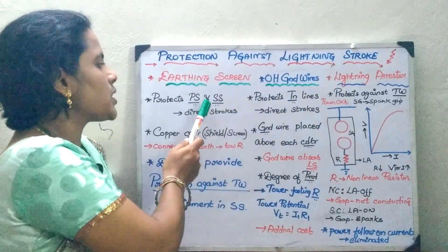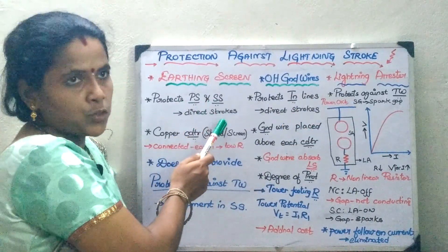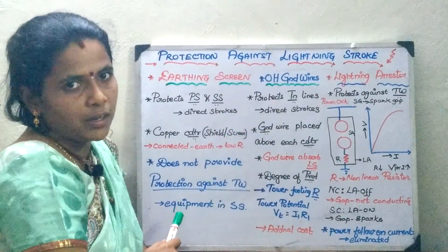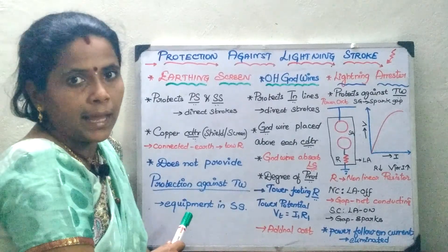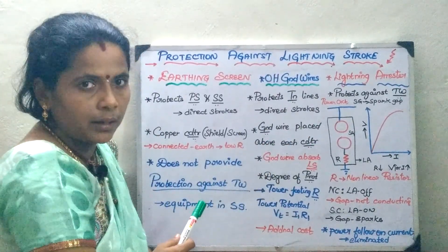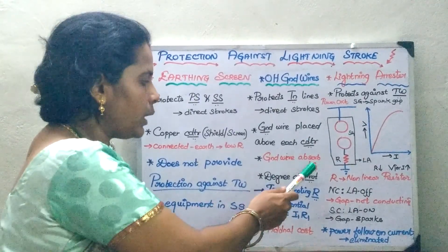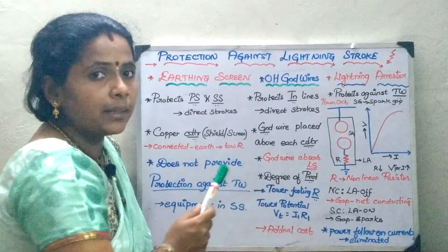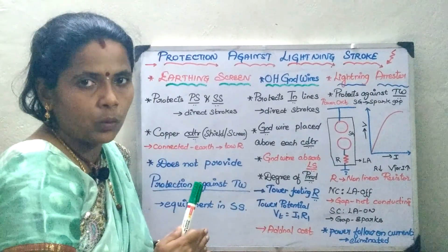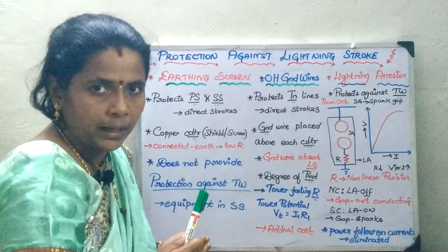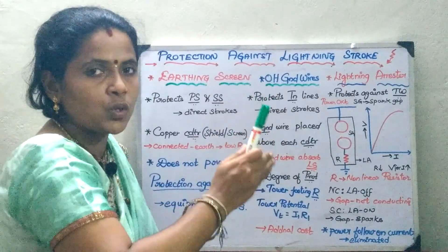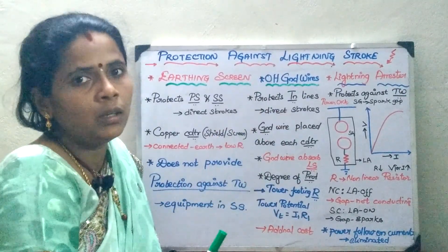The earthing screen protects the power station and the substation against direct strokes, whereas the overhead ground lines give protection for your transmission lines. You are going to place a ground wire above each conductor. This ground wire is going to absorb the lightning surges. One concept to note is what degree the overhead ground wires are going to protect — it is going to depend upon the tower footing resistance.